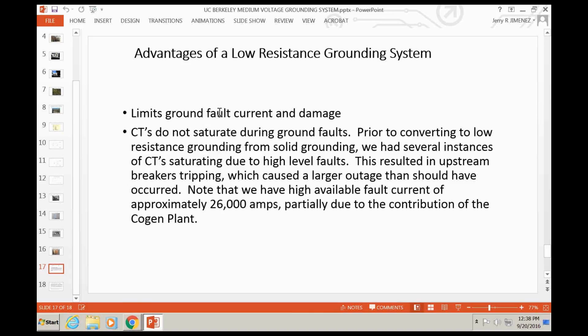Yep. Now here's the other thing that I didn't know about till I got a chance to be here for a while and observe some faults and analyze these fault records. And this is really important. The CTs do not saturate during ground faults on our system.